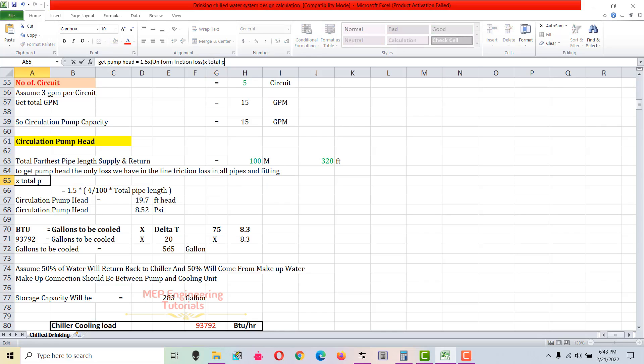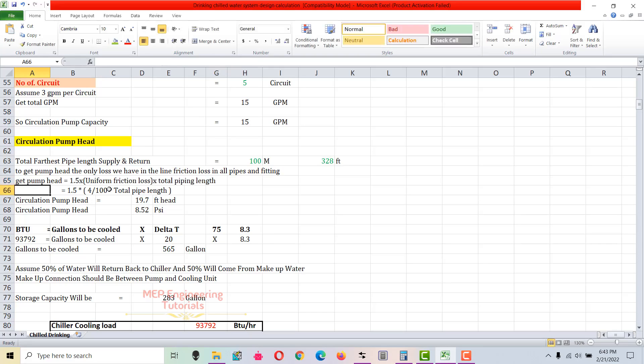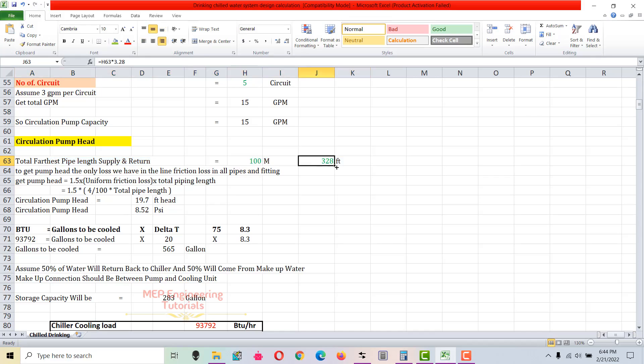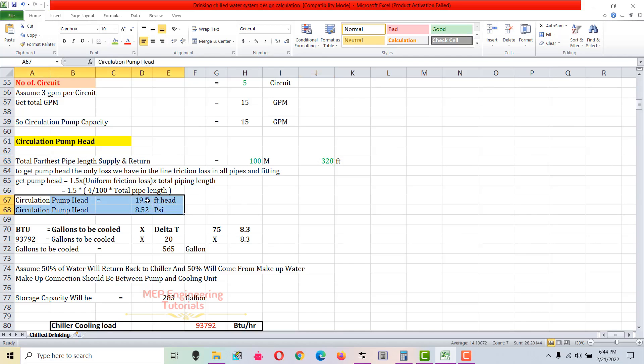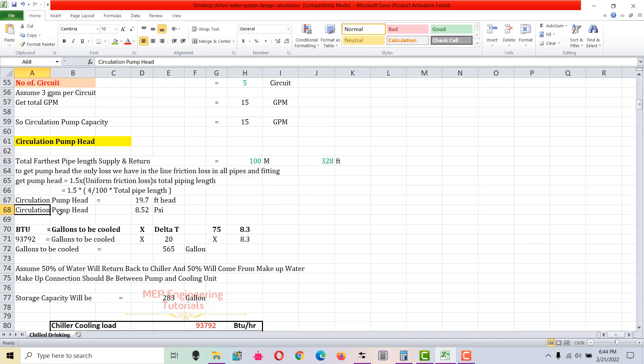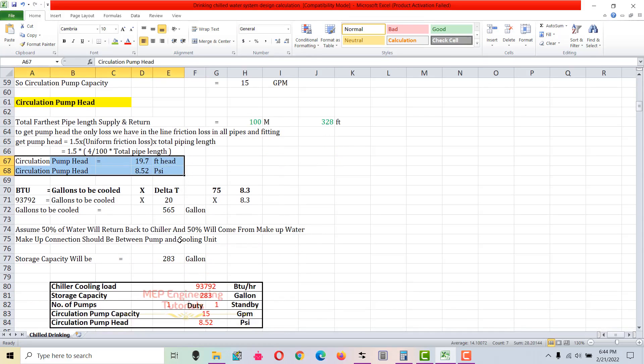The formula is: head = 1.5 × (4/100) × total piping length. You go to the drawing and check the furthest piping length from the circulation pump to the furthest outlet. Let's say it's 100 meters, which equals 328 feet. So circulation pump head = 1.5 × (4/100) × 328 = 19.7 feet. To convert to PSI, multiply by 0.433, giving the head loss in PSI.